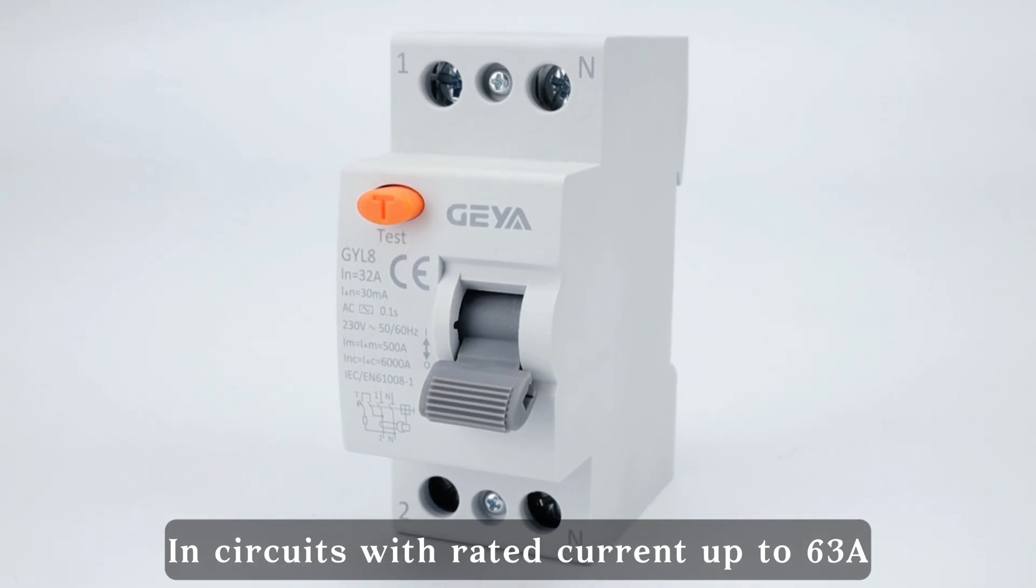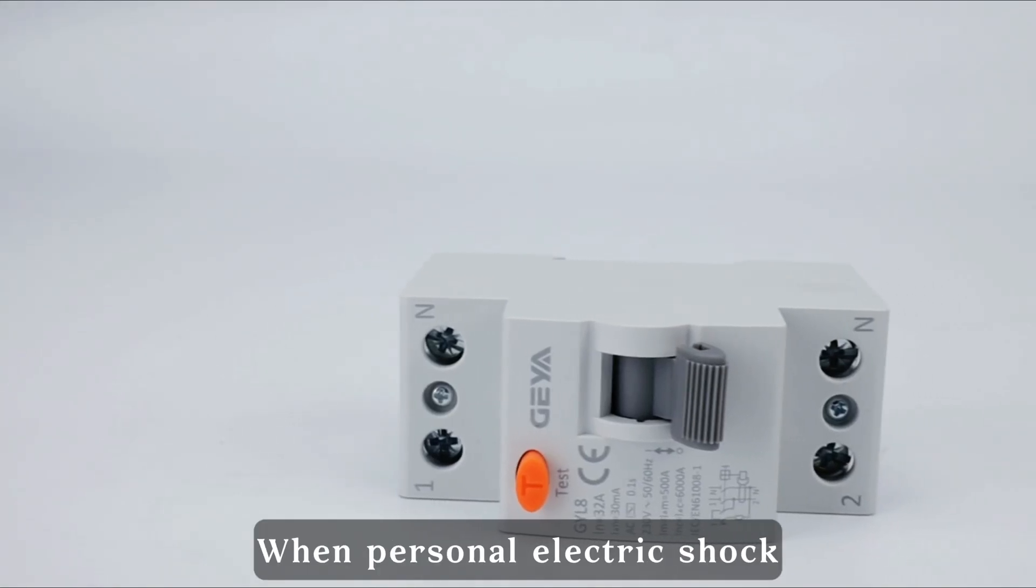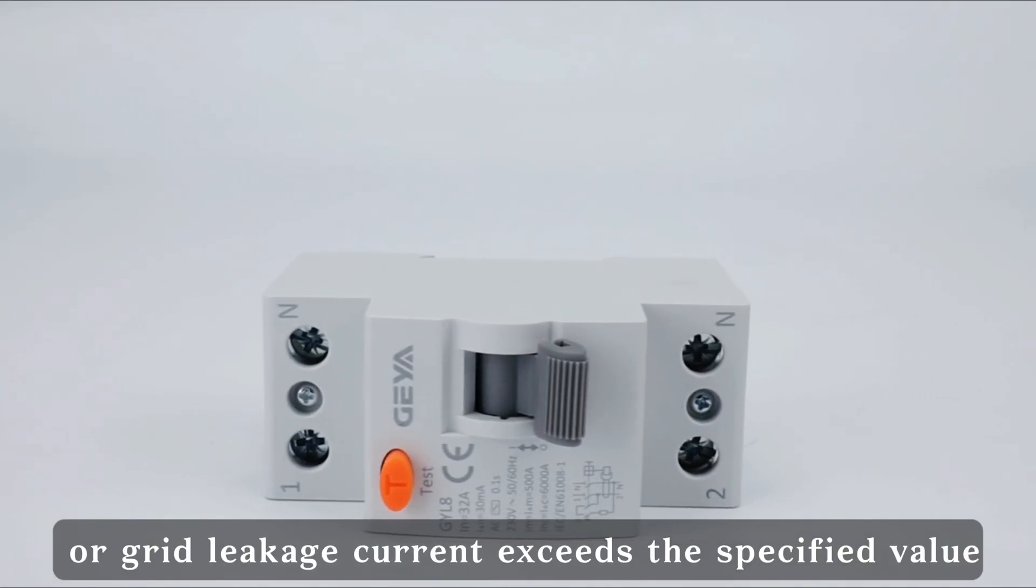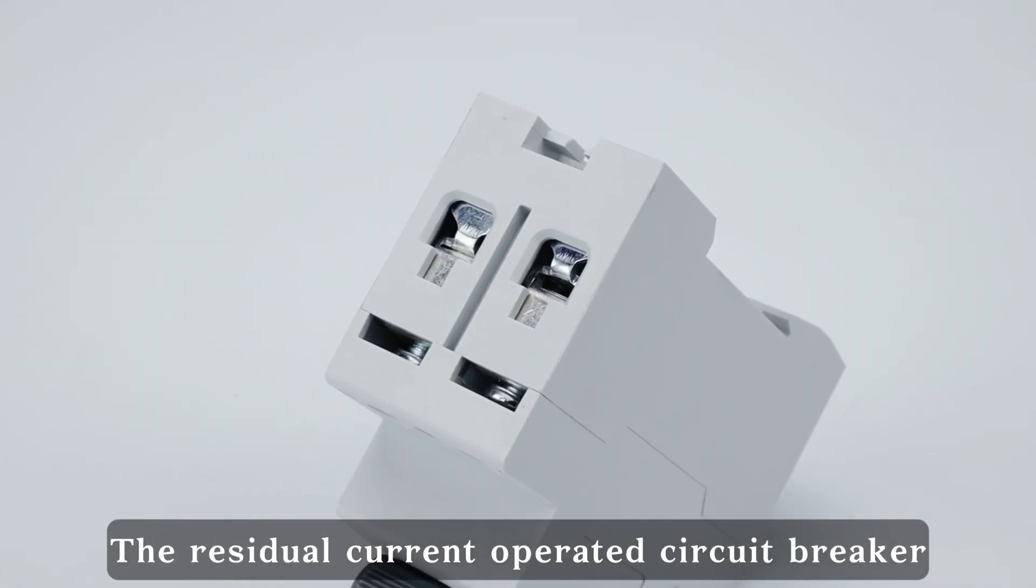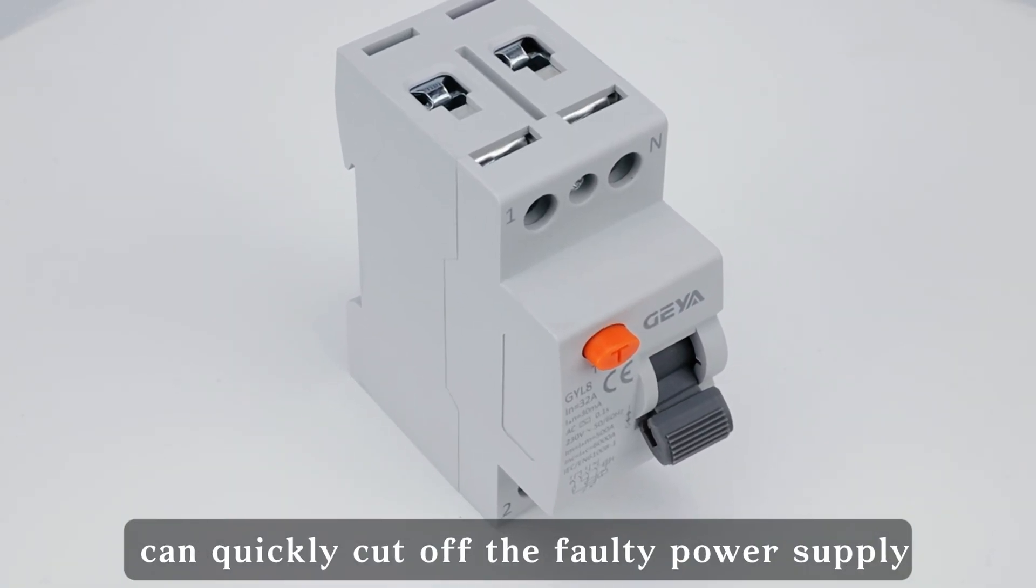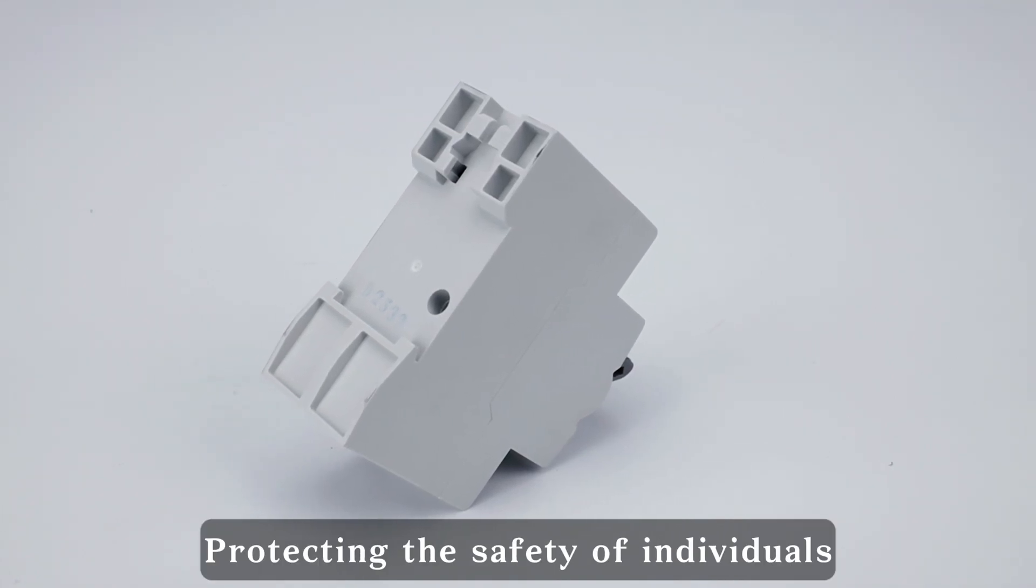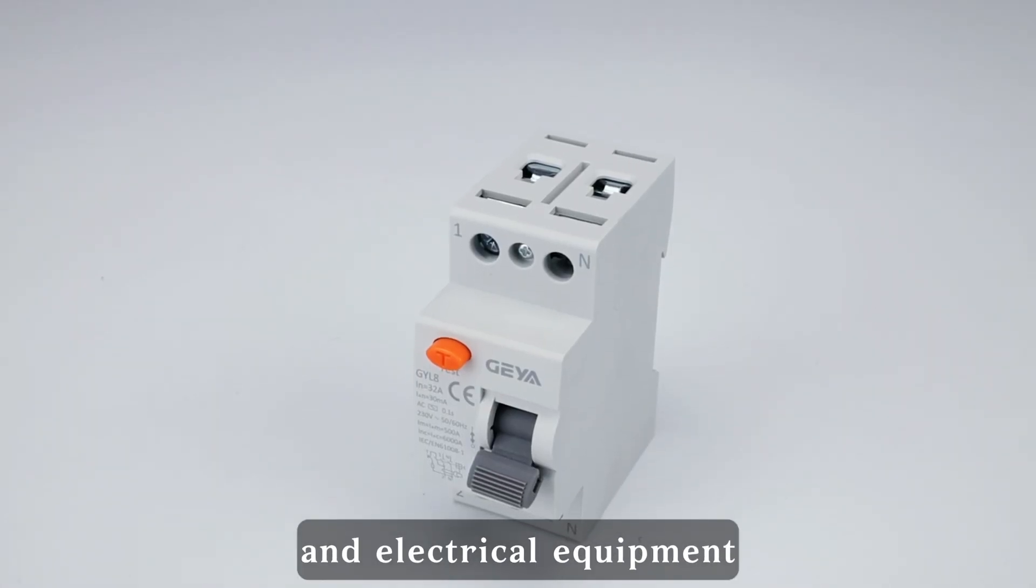In circuits with rated current up to 63A, when personal electric shock or grid leakage current exceeds the specified value, the residual current operated circuit breaker can quickly cut off the faulty power supply in a very short time, protecting the safety of individuals and electrical equipment.